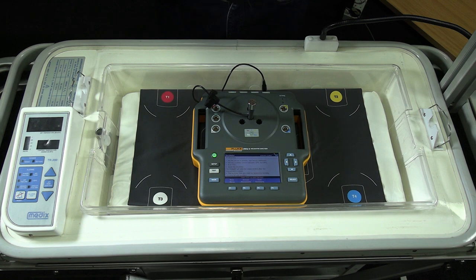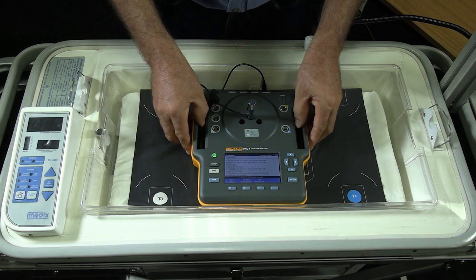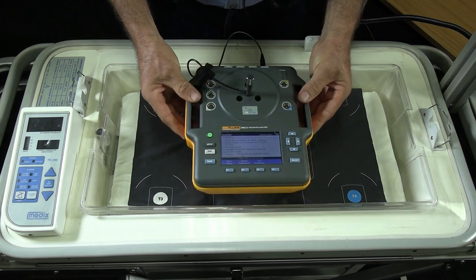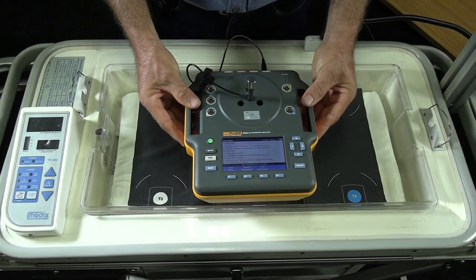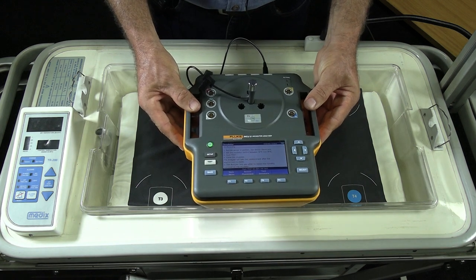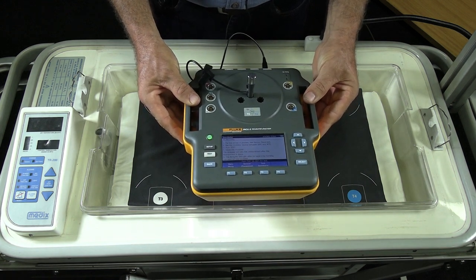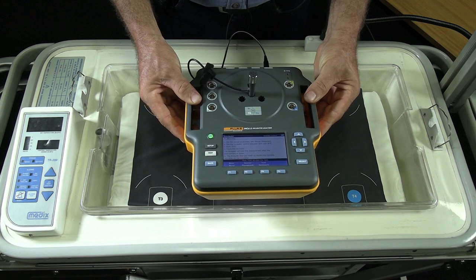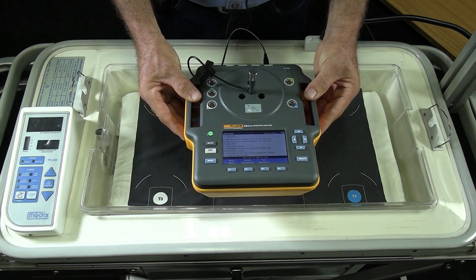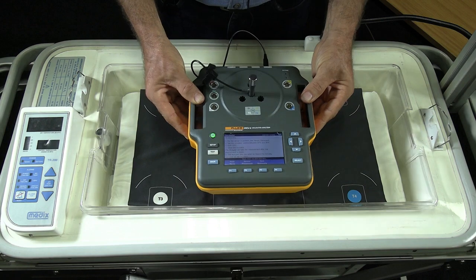For that, we're going to place the unit in the middle of the incubator, and we're going to close the hood. Then we've got an outside environmental test where we will be taking this unit, moving it outside of our incubator, 3 meters away from the incubator and 1.5 meters above ground. From there we'll be doing the outside environmental sound testing.